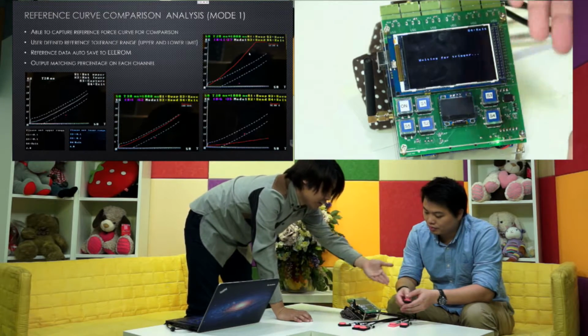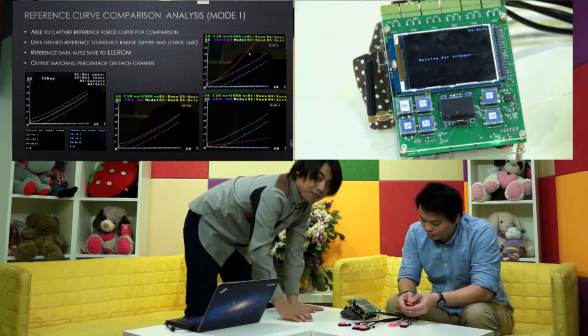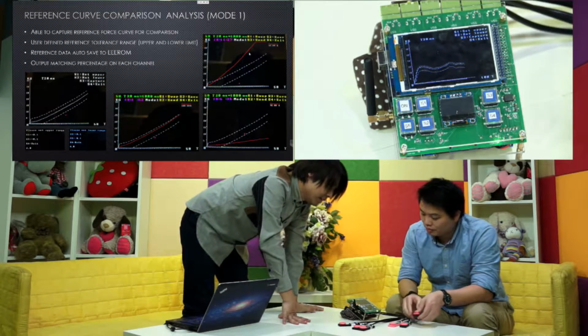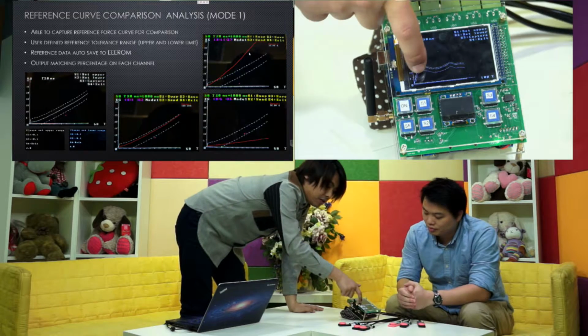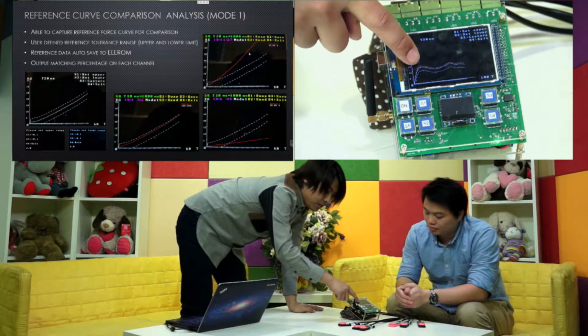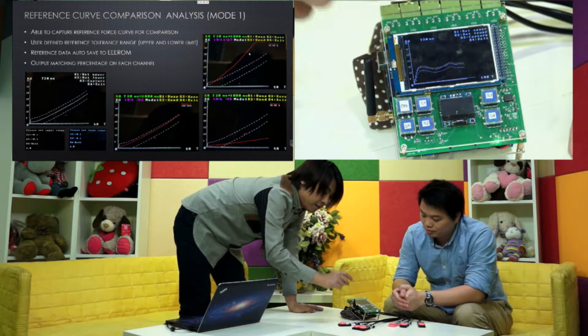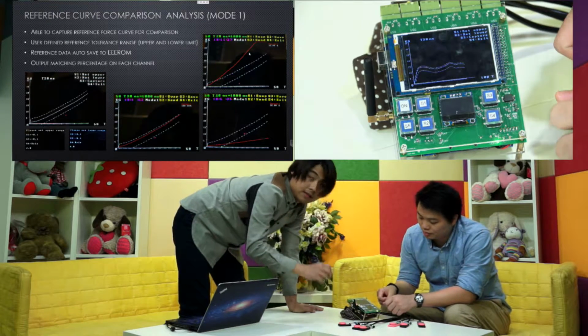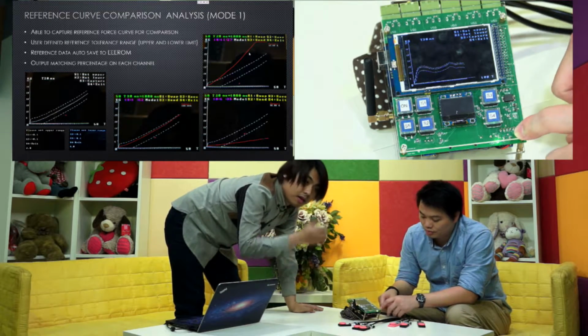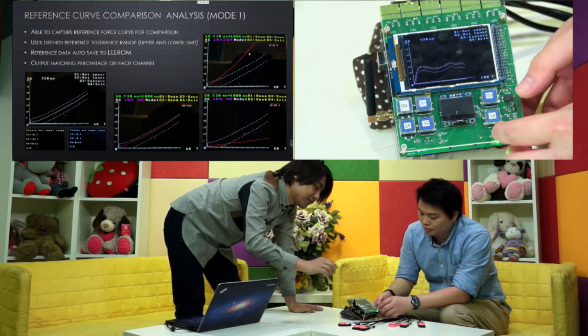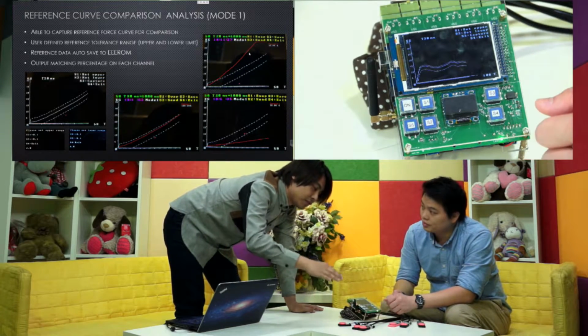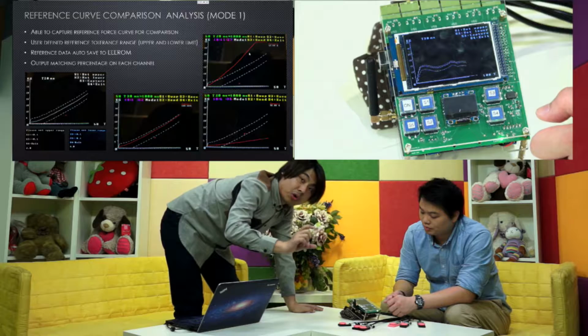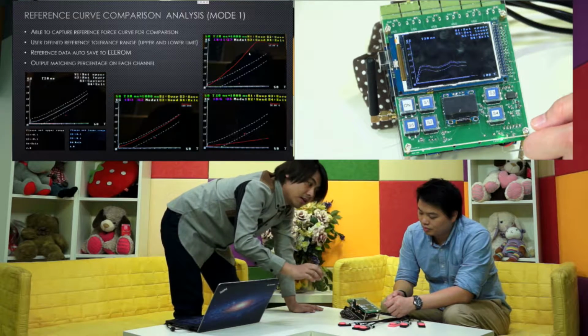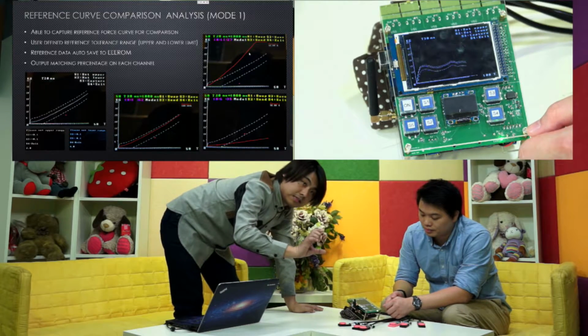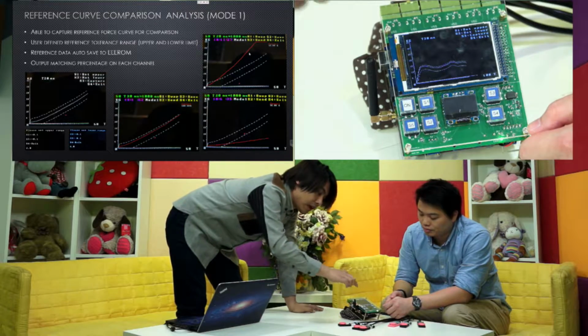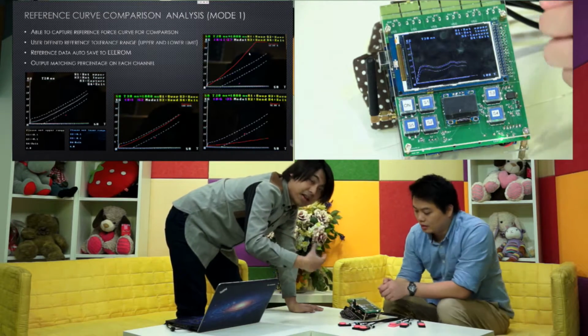Then we just put some force as a reference. Okay, this reference curve is here. You can see the upper and lower have a dot line—this is the tolerance. You can't only just accept using the reference curve; you need to apply some tolerance to it. Then if the testing sample is within this range, that is a match.